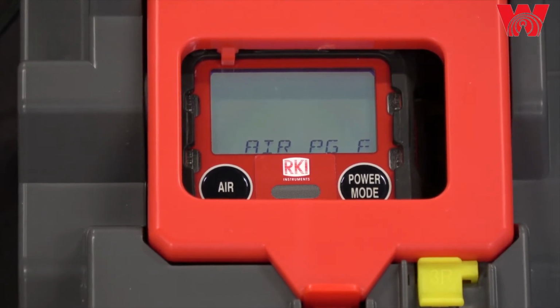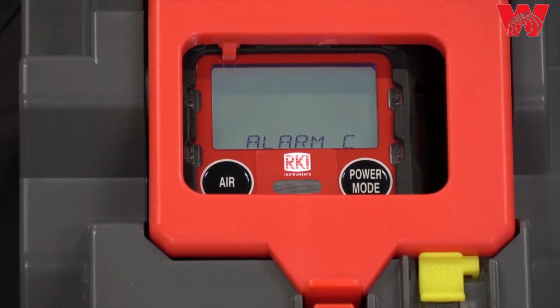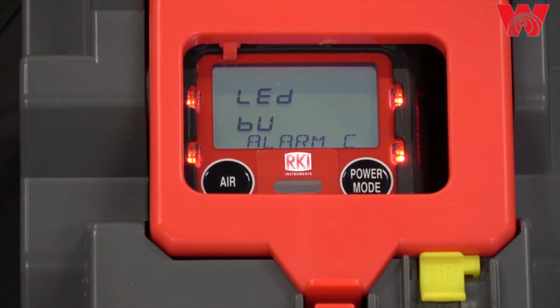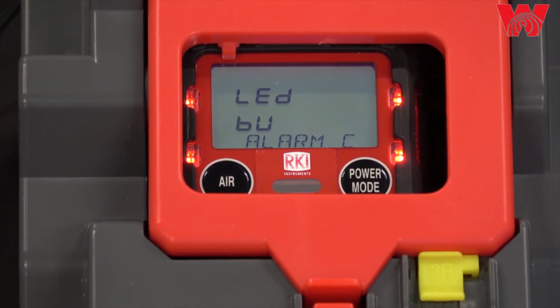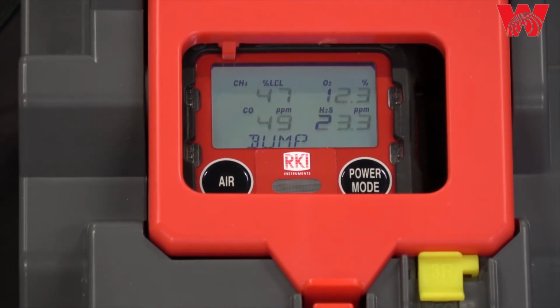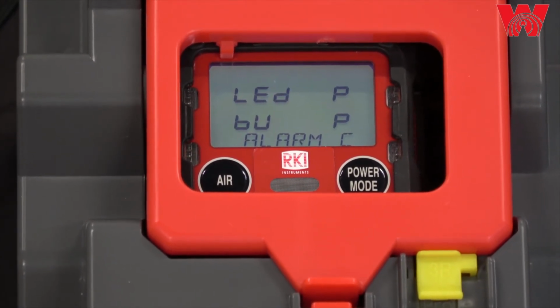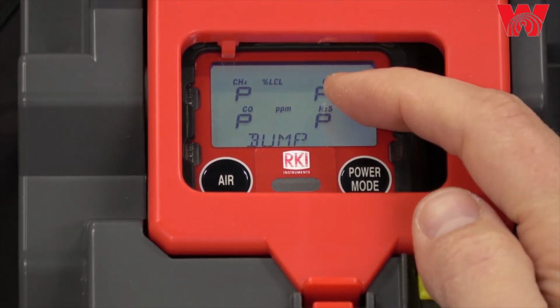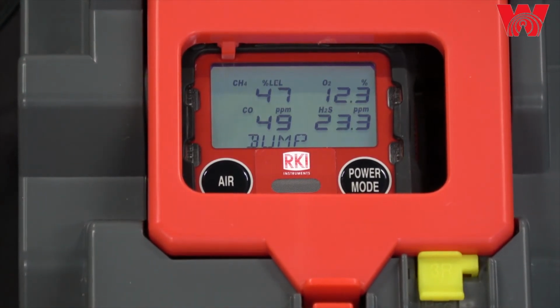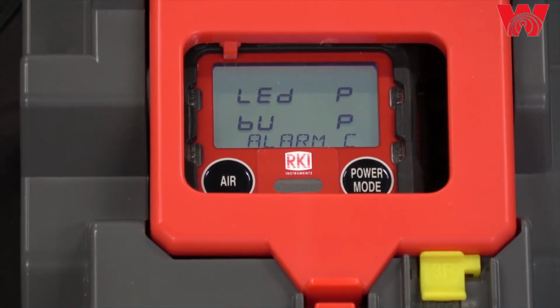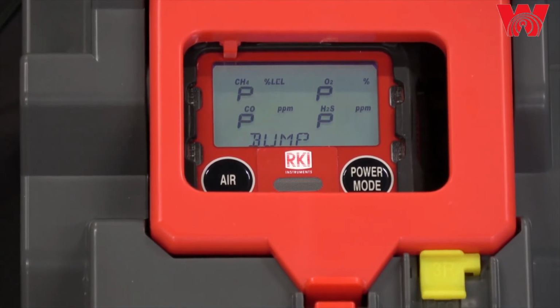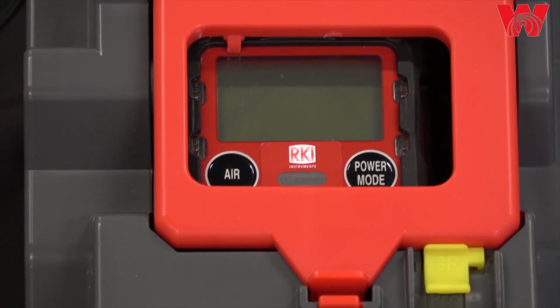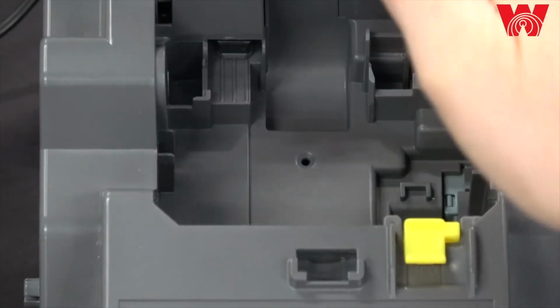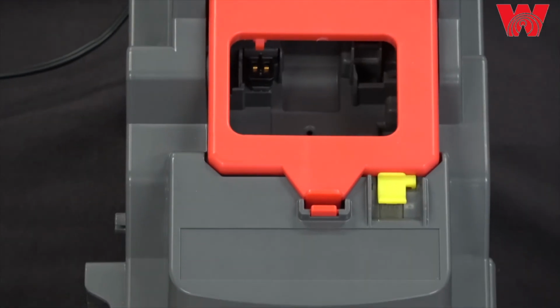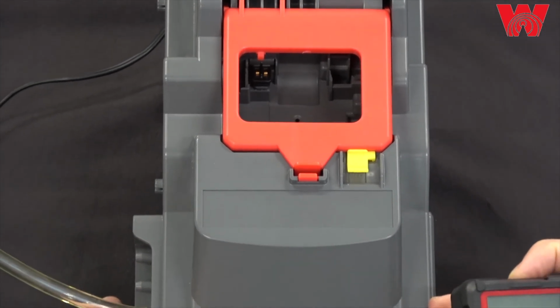Now the SDM is flushing with fresh air to get all of that calibration gas out, doing an alarm check. And here are the bump test results. So these were the bump readings, the actual result, and then the LED and buzzer check results. Since everything was successful, the instrument will be shut off, and we can remove it. And that is how you calibrate and bump test a GX3R in an SDM-3R docking station.